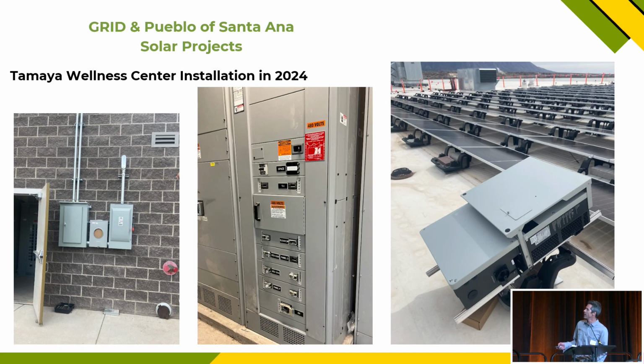So this is at the Wellness Center. Without going too into the weeds, we installed the inverters on the roof, then went down the north exterior wall to a load center where the inverter outputs get combined. It goes through a PNM meter, an AC disconnect, and then right there is our point of interconnection. Fortunately, the electrical service there was a 1600 amp service, and we were able to interconnect with a 200 amp breaker, with more capacity available for phase two, which is great. This was a really clean, great install. It was a privilege to work with the Pueblo of Santa Ana, and we appreciated all of their help and support with the project. One thing to note is that they did have a backup generator.